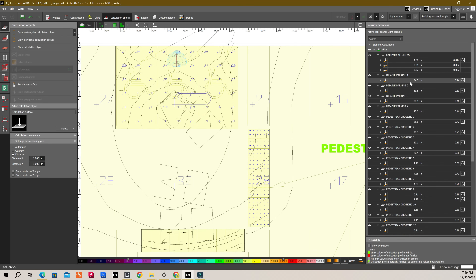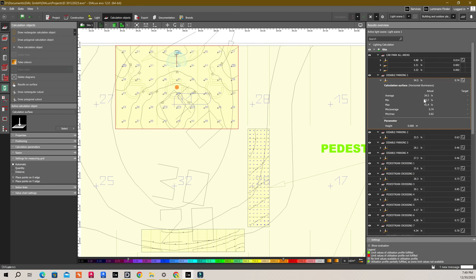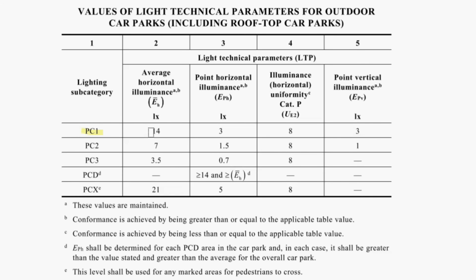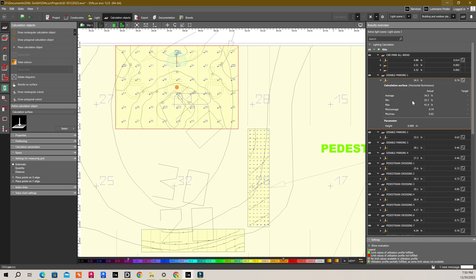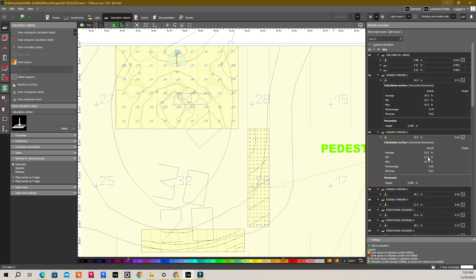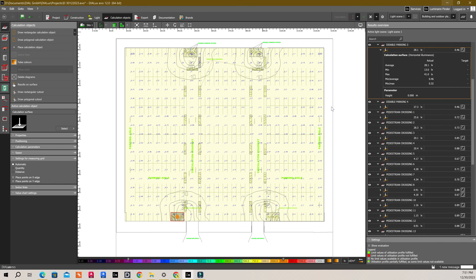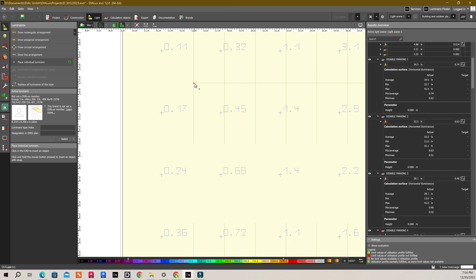You can see that for disabled car park 1, the minimum value is greater than 25, which is greater than 14. As you can see, the minimum horizontal illuminance for the disabled car park must be greater than or equal to 14 and greater than or equal to the average horizontal illuminance for the overall car park. Disabled parking 2, 3 and 4 are also greater than or equal to 14. So let's start adding the lights for the rest of the car park as well.